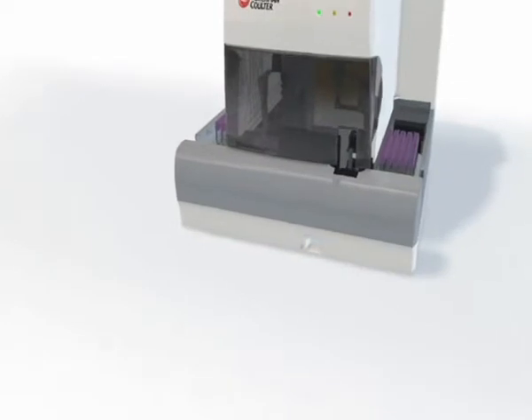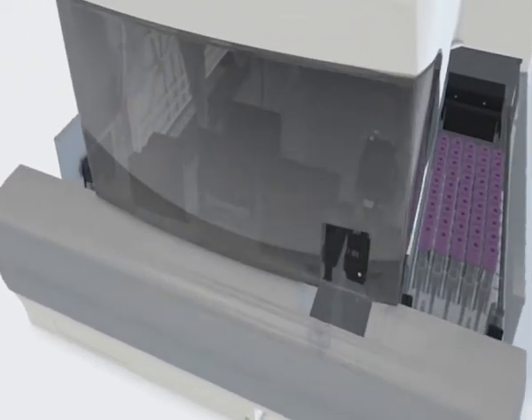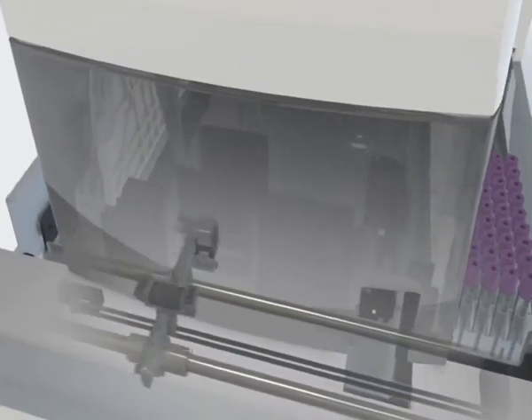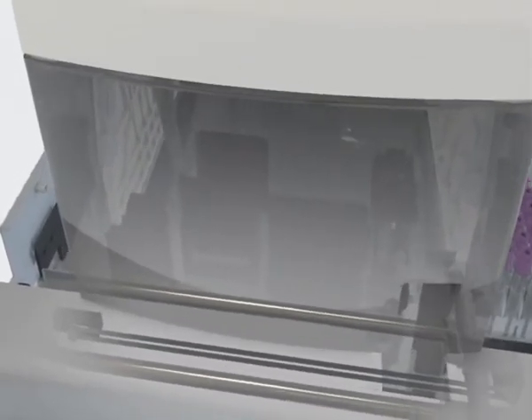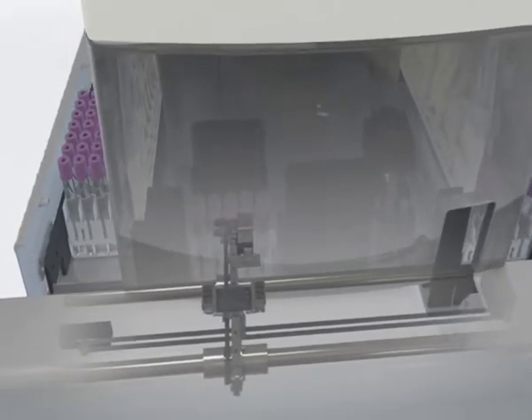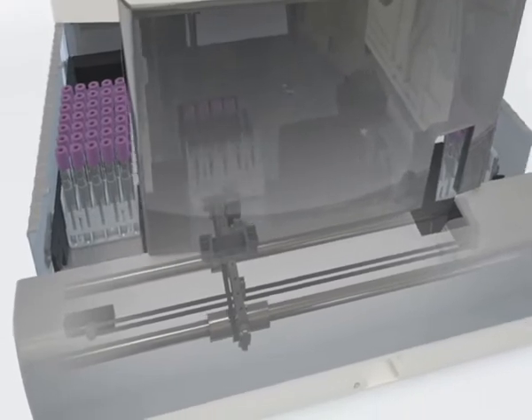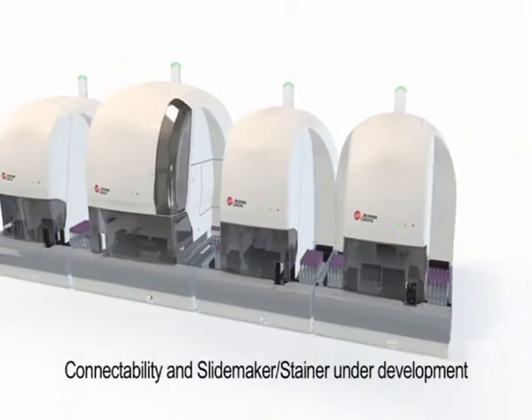The analytical module of the UniCel DxH 800 contains a state-of-the-art specimen transport module. This specimen transport module uses magnetic force to move cassettes from one location to another, with no exposed moving parts, for maximum operator safety.